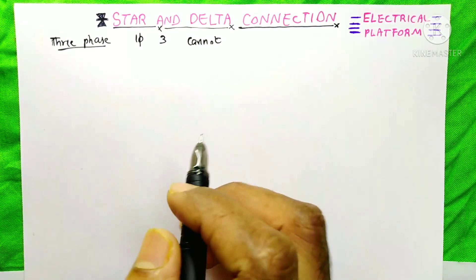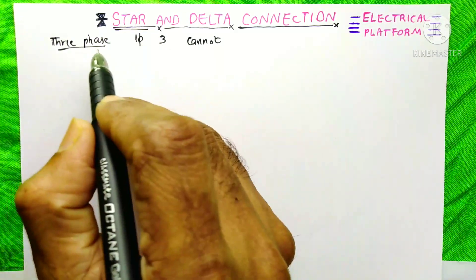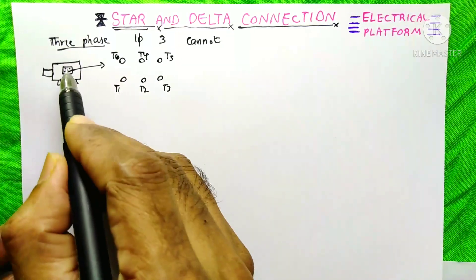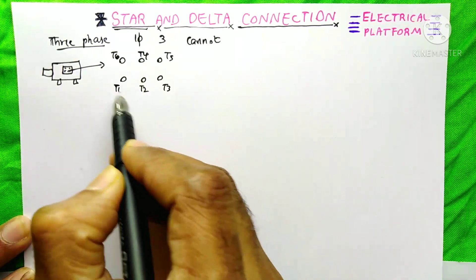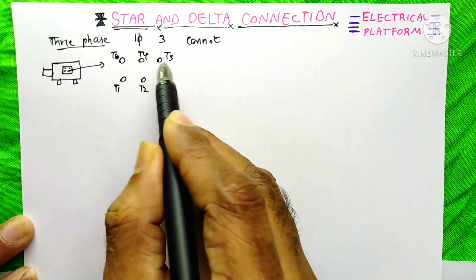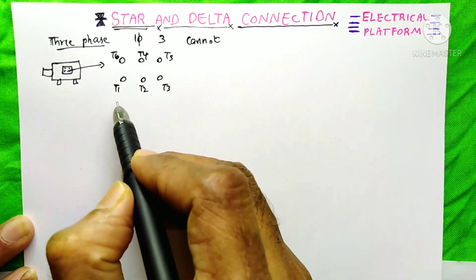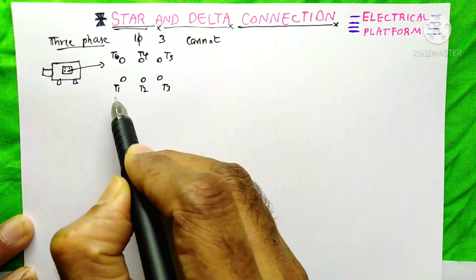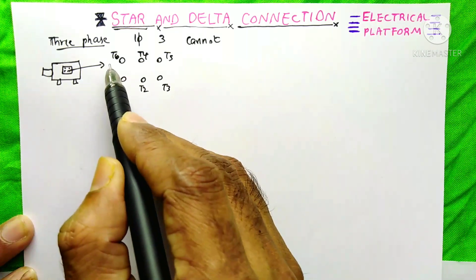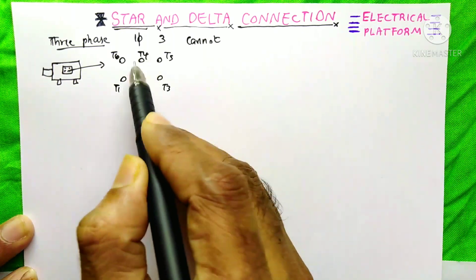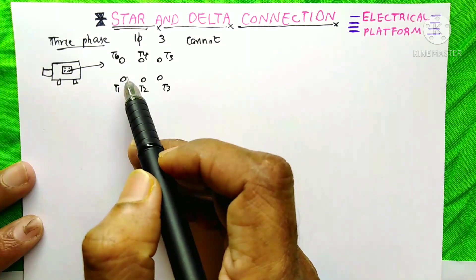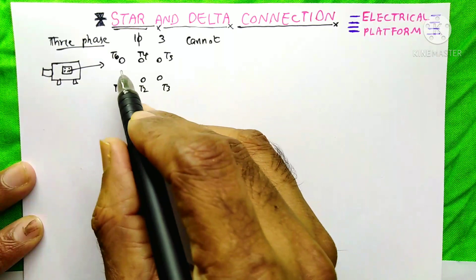If you want to get deep information about star and delta, please stay on this channel till the end of this video without skipping. It is a three-phase motor and this is its terminal box. The terminals are given as T1, T2, T3, T4, T5, T6. You may wonder that T1, T2, T3 are in sequence from the left, but T4 starts from the middle. This arrangement is to make the delta connection symbol, which I will explain later.